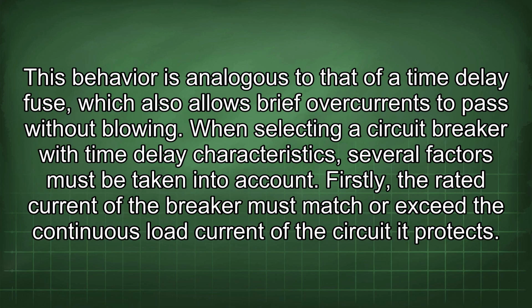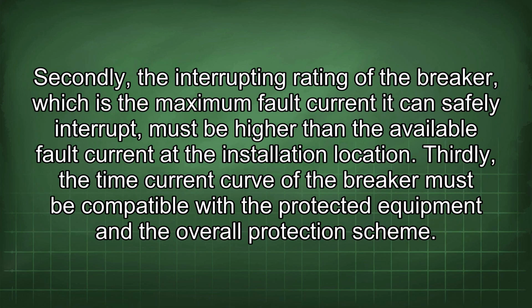When selecting a circuit breaker with time delay characteristics, several factors must be taken into account. Firstly, the rated current of the breaker must match or exceed the continuous load current of the circuit it protects. Secondly, the interrupting rating of the breaker, which is the maximum fault current it can safely interrupt, must be higher than the available fault current at the installation location. Thirdly, the time current curve of the breaker must be compatible with the protected equipment and the overall protection scheme.